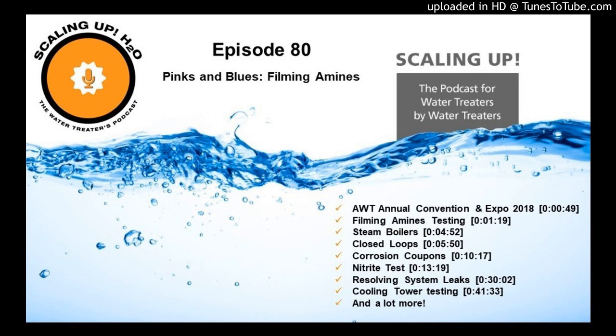But nobody thought about the water treater's perspective. So now we have copper in the system, we have mild steel in the system, and now we have this boiler that's made out of aluminum. Well, folks, each one of those metals is treated differently and in a pH environment that the other metal does not like. So you've got to pick one.